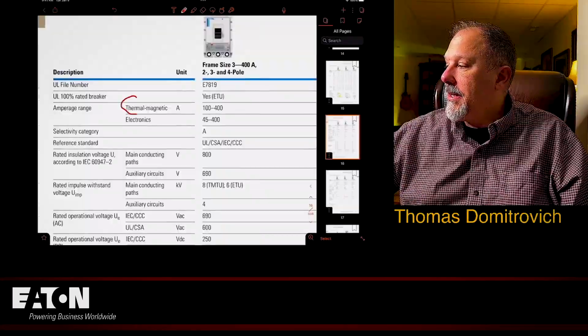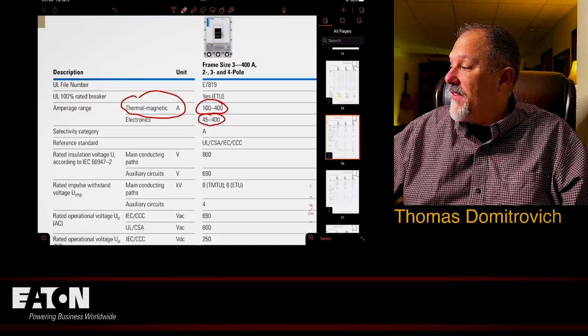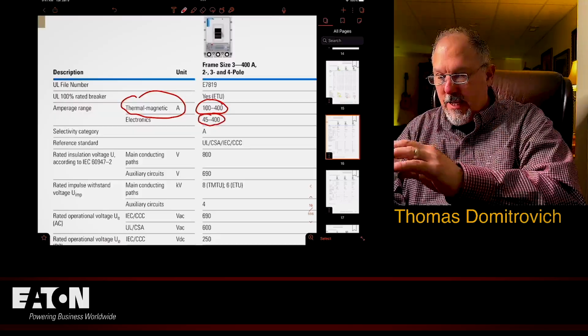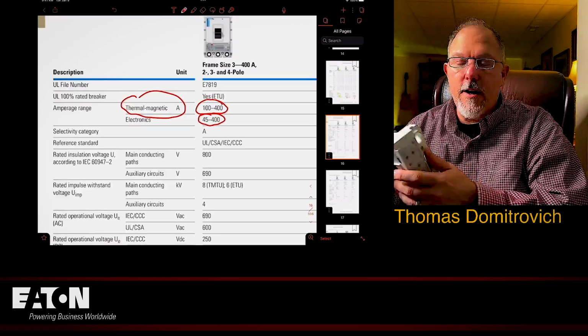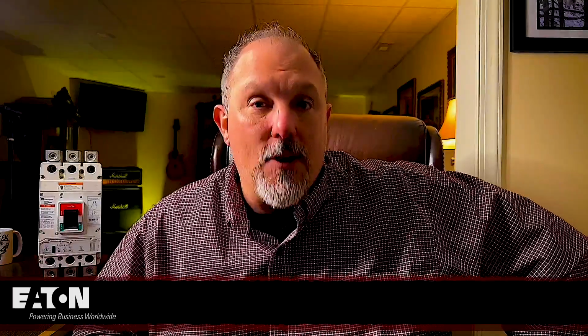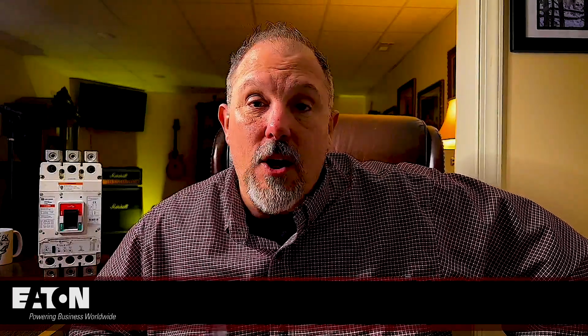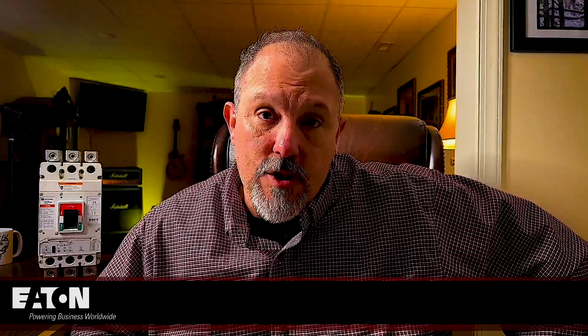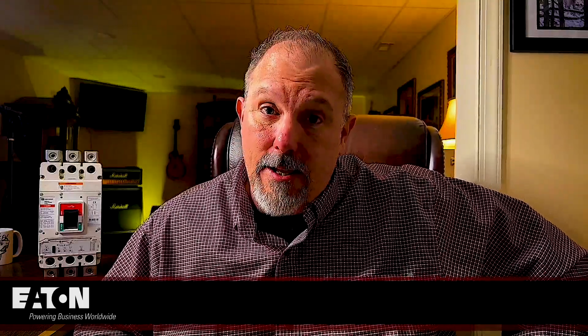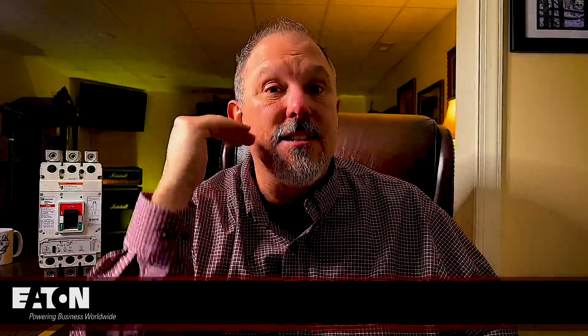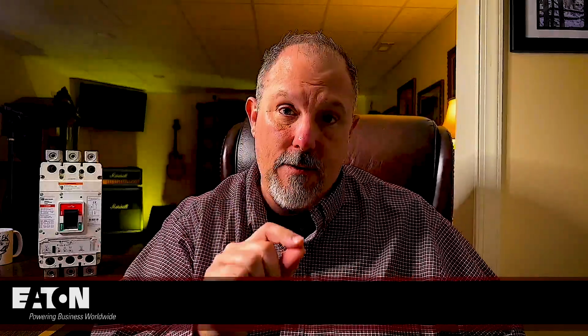but thermomagnetic down to 100 amps, down to 45 amps on electronics. That means you take a device like this, and it's a 400 amp frame breaker. And then based on Article 240, I can adjust it down to 100 amps, put 100 amps worth of conductor on it, and that becomes a 100 amp rated breaker. And I have an arc flash reduction maintenance switch on it. But it works at 2 times off of the 400 amps. So the arc flash reduction maintenance switch would pick up somewhere around 800 amps, maybe a little bit higher than 800 amps. But that is a pretty doggone low setting to provide reduction of incident energy. It reduces risk because it reduces the severity, not the likelihood, it reduces severity.